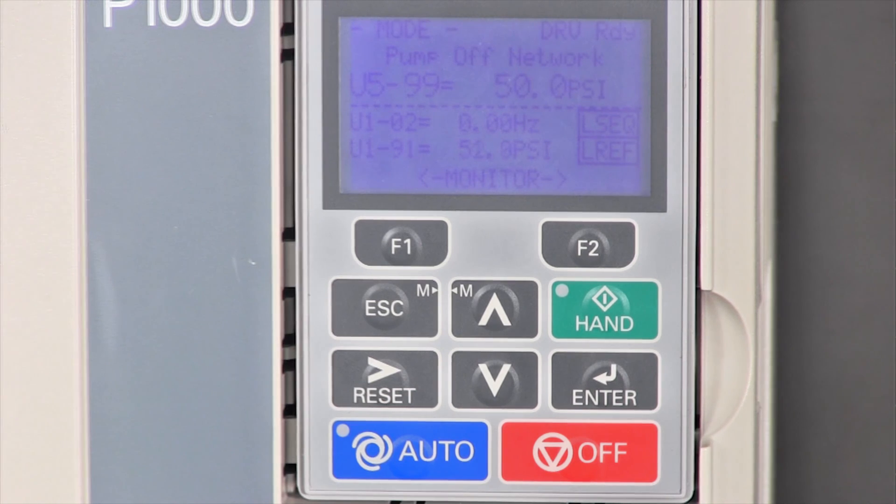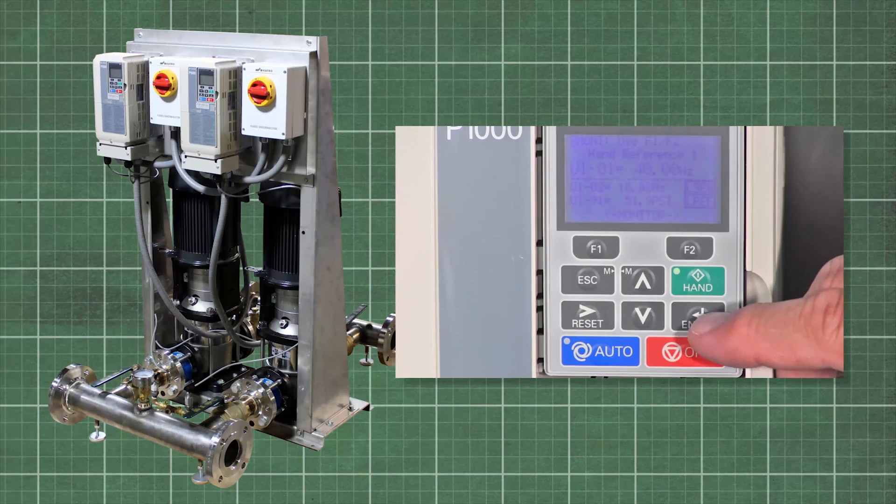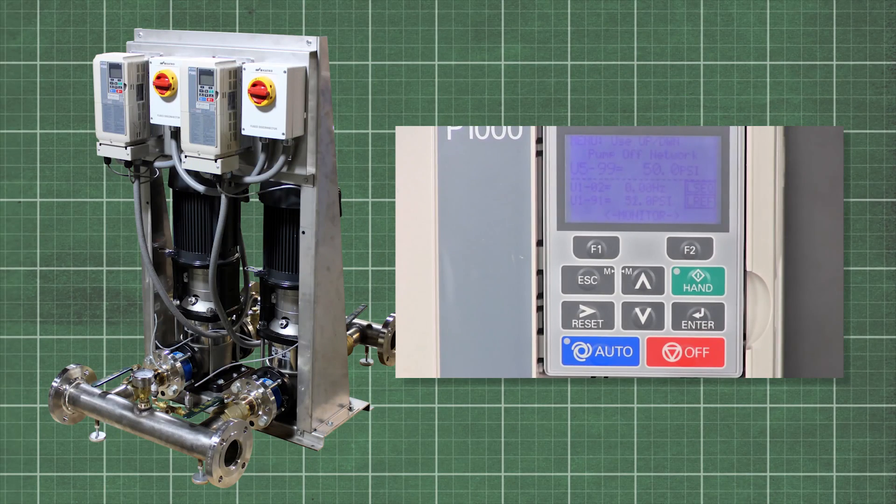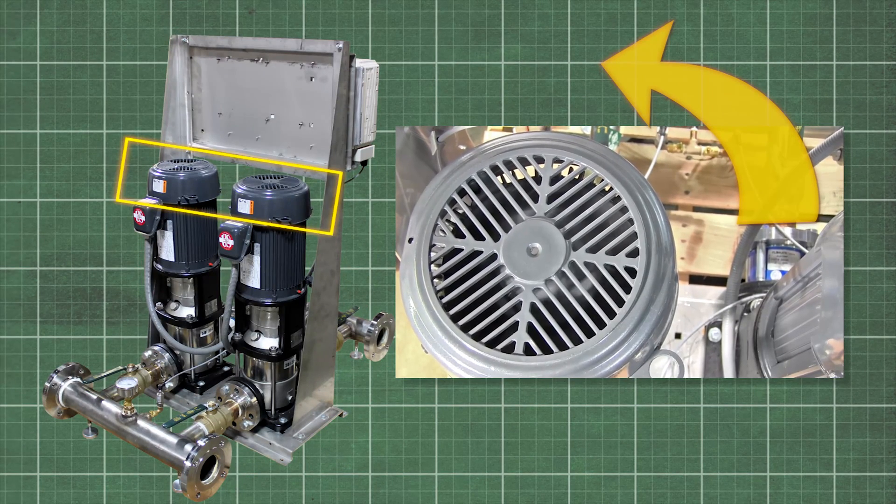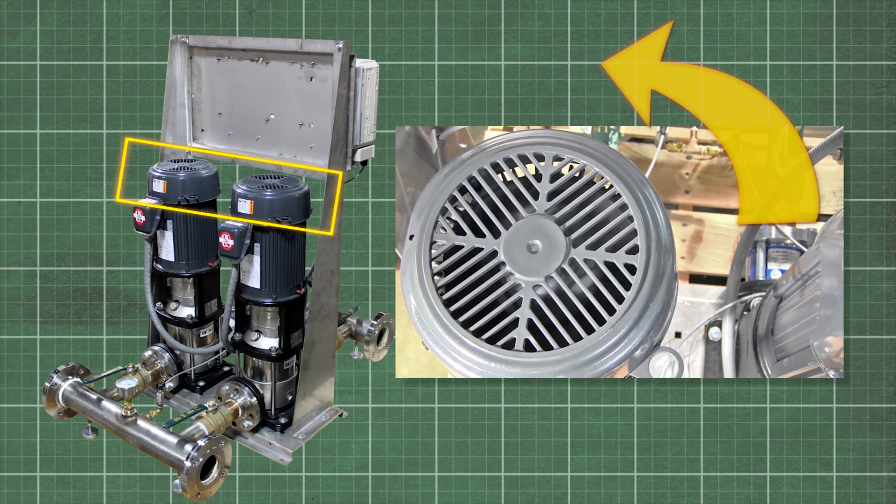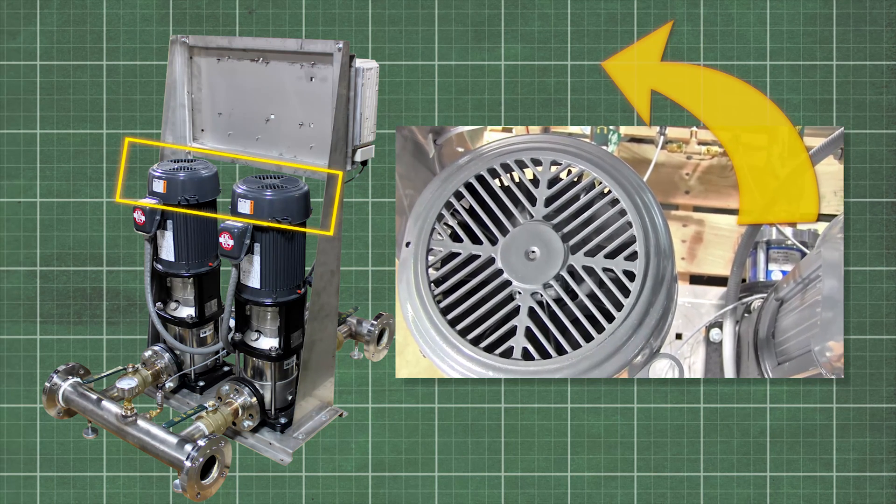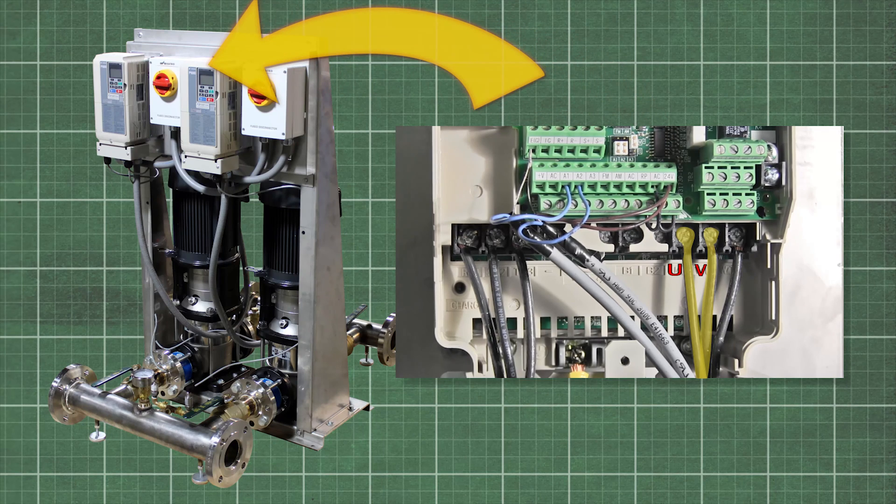Before we run into the auto mode, let's double check the motor rotation. Press the hand button on and then off. Look at the end of the motor. The motor fan should be turning in the direction of the arrow on the pump. For this pump, it should be turning counter clockwise. If not, switch the U and V wire inside the drive on the UVW terminals.